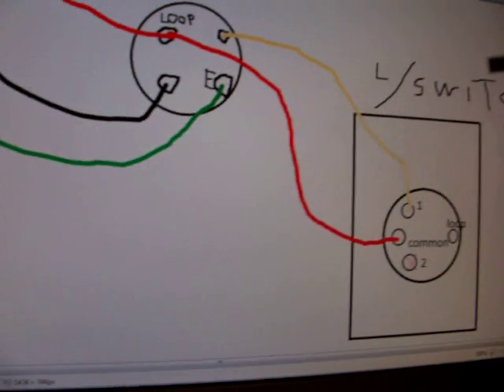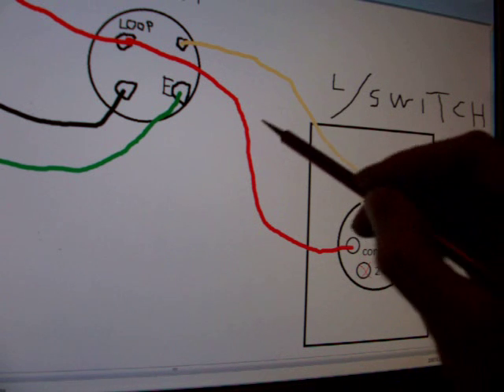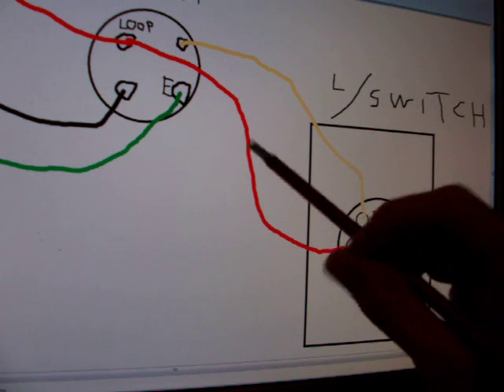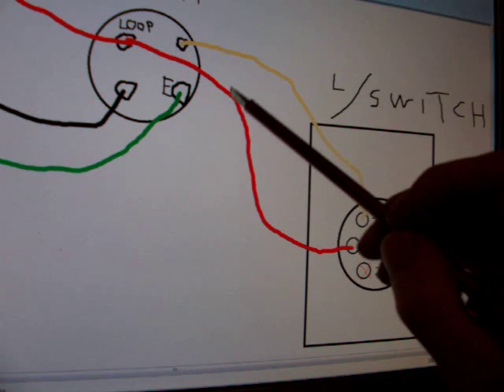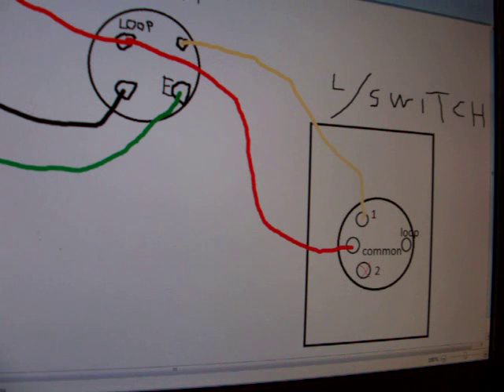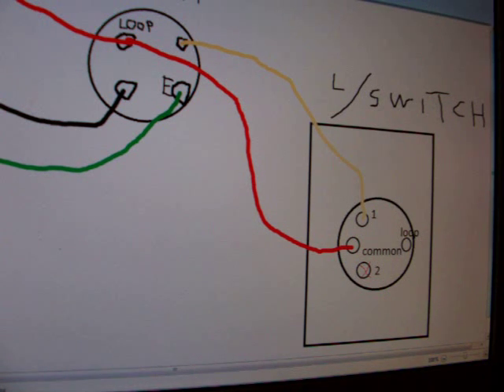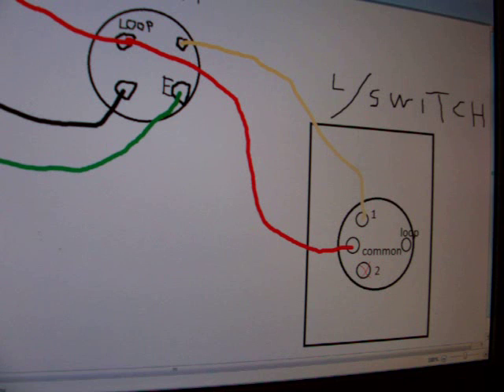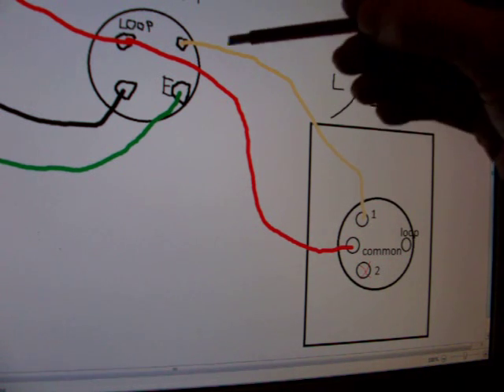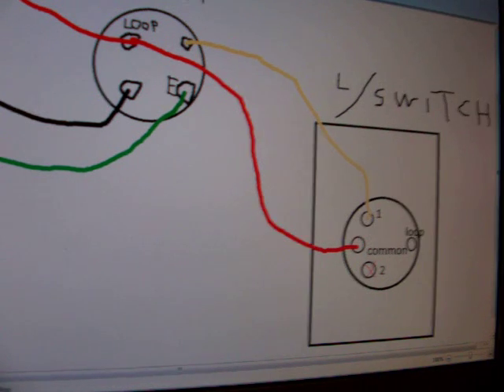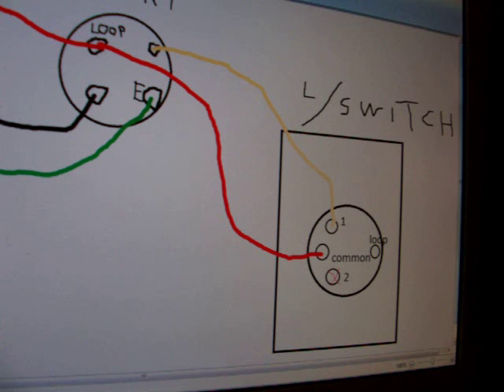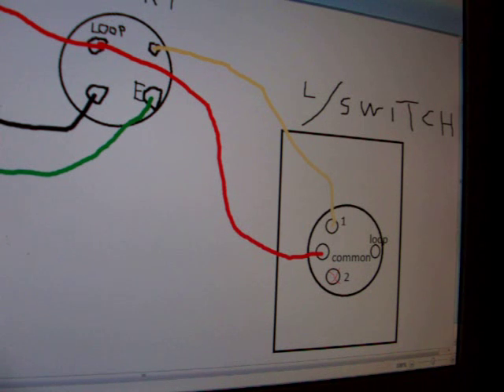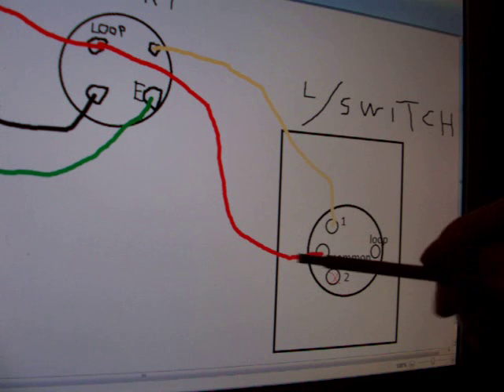So anyway, your active continues down to the switch. So this is actually a separate wire. You'd have a two pair conductor. You'd have a white and red. Now in Australia, it is illegal to use a black or a green wire as an active. You have to use, preferably if it's a switched wire, in light circuits, they generally use a white conductor. And that generally means that the conductor's switched and not a conductor that's always live. But you can't take anything for granted, can you?